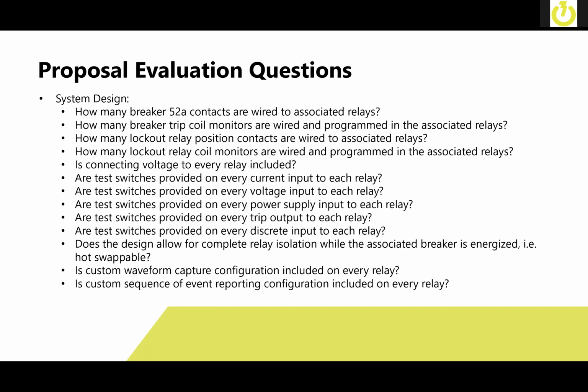and you can quickly alert your operators and maintenance crew to get that fixed. From a test switch standpoint, are they being provided on all current inputs to each relay and on all voltage inputs to each relay? That allows you to simulate the system or isolate the system as necessary, or you can inject your own current and voltage during testing easily without having to modify the wiring and disconnect the existing system. Test switches provided on power supply inputs to the relays. Are test switches necessary on every trip output? Are test switches necessary on every discrete input to each relay?